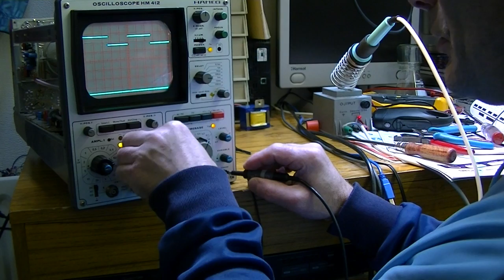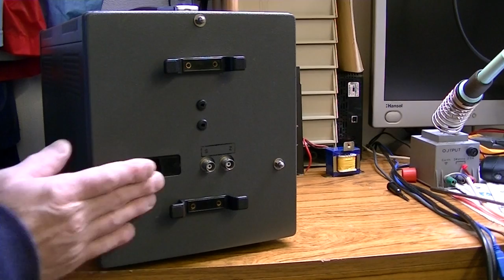Trigger in channel 2, trigger source channel 2. Yeah, beautiful. Now this oscilloscope's not earthed - the mains plug for it does not have the earth connection. It has its plus points and its bad points of using a scope that's not earthed, of course, but it also means you can clip your negative lead of your scope probe onto a hot chassis on something without blowing your probes up.